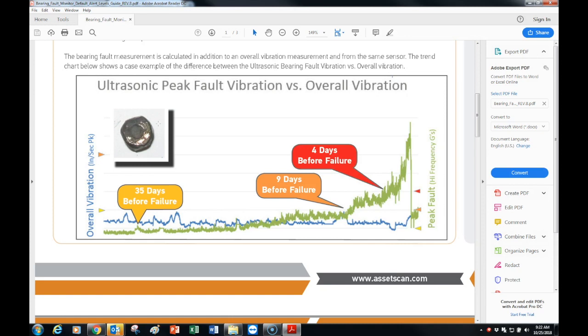And so what we're demonstrating here is the value of that early indicator, that leading indicator of ultrasonic versus overall vibration. In this case the overall vibration hovered along here and really did not show any indication of this oncoming fault.